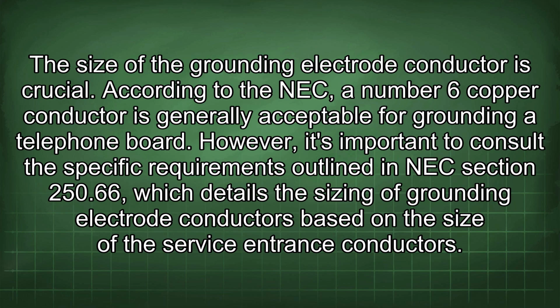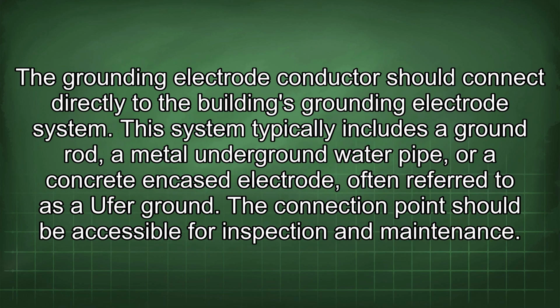However, it's important to consult the specific requirements outlined in NEC section 250.66, which details the sizing of grounding electrode conductors based on the size of the service entrance conductors. The grounding electrode conductor should connect directly to the building's grounding electrode system. This system typically includes a ground rod, a metal underground water pipe, or a concrete encased electrode, often referred to as a Ufer ground. The connection point should be accessible for inspection and maintenance.